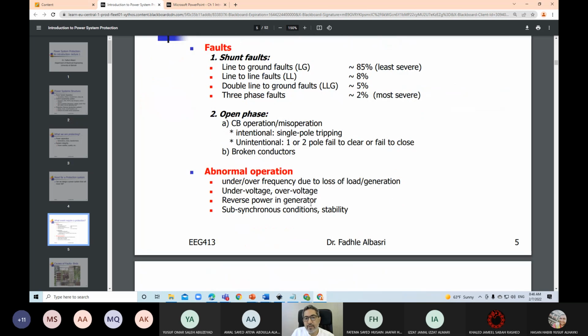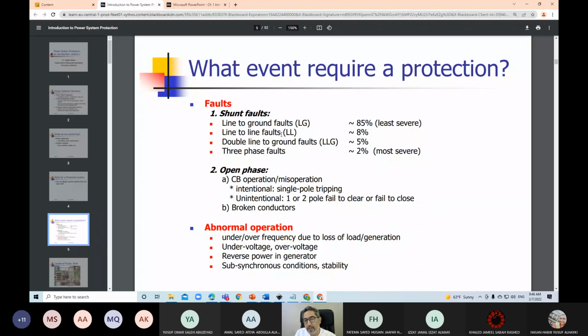Now, what are the faults that we are protecting against? We are trying to detect short circuits in the systems. The short circuits generally could be line-to-ground faults, and this is the most general type of fault that can occur. Or it could be a line-to-line fault, in a three-phase system, a fault between line 1 and line 2, which represents 8% of faults. It could be double line-to-ground faults, or it could be three-phase faults. Three-phase faults are the least common, but they are the most severe in terms of current magnitude and damage that could be caused to the equipment.